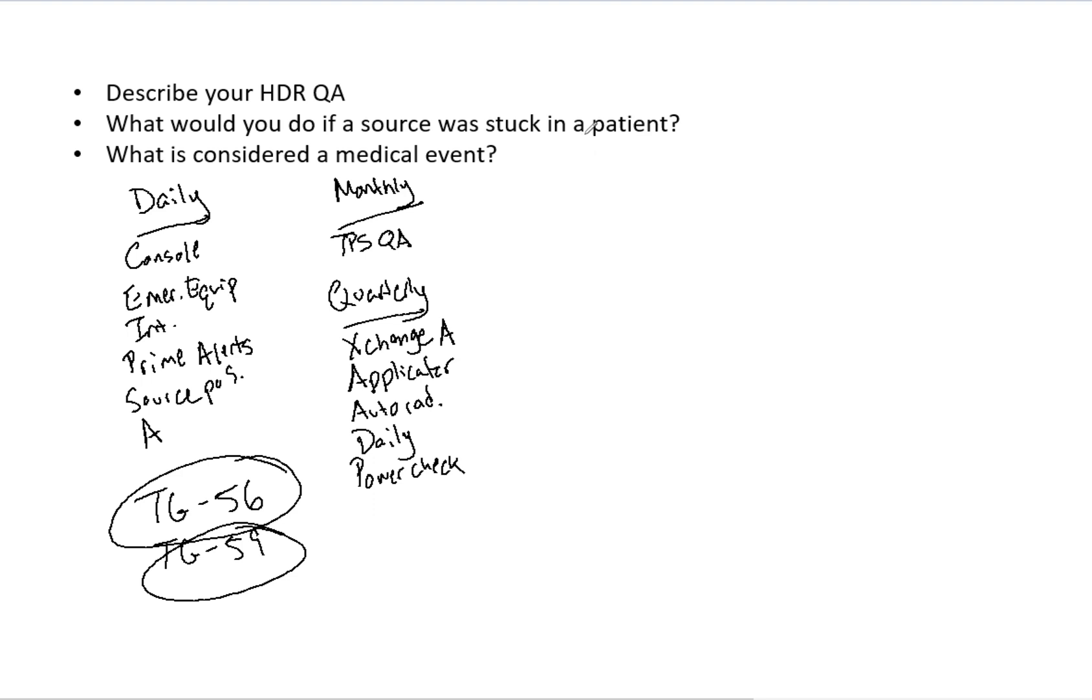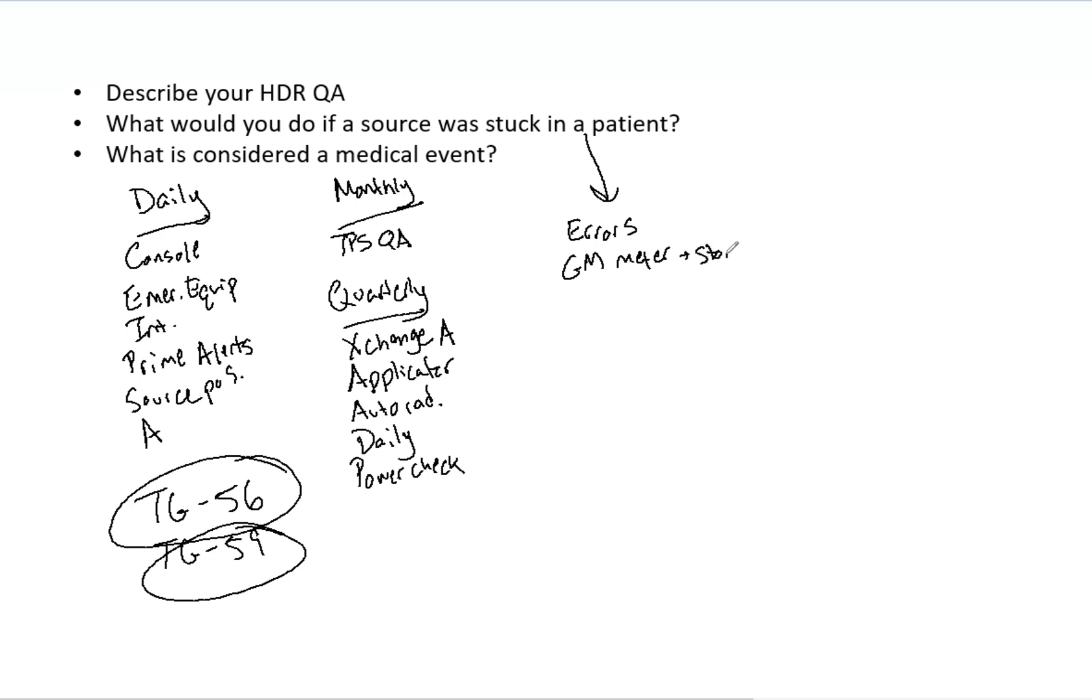So what would you do if a source was stuck in a patient? So first thing you want to look for any errors on the console. You want to go into the room with the GM meter. This is going to help you determine if the source is out. You of course have your prime alerts and things of that nature, but you also need your stopwatch. Remember that because of the high dead times, you're not necessarily going to get a necessarily accurate dose rate or exposure rate from the GM meter, but it will tell you if the source is still out and give you some type of instantaneous exposure rate.